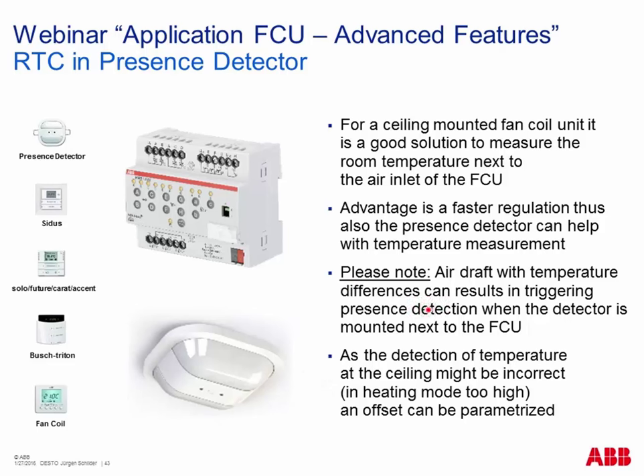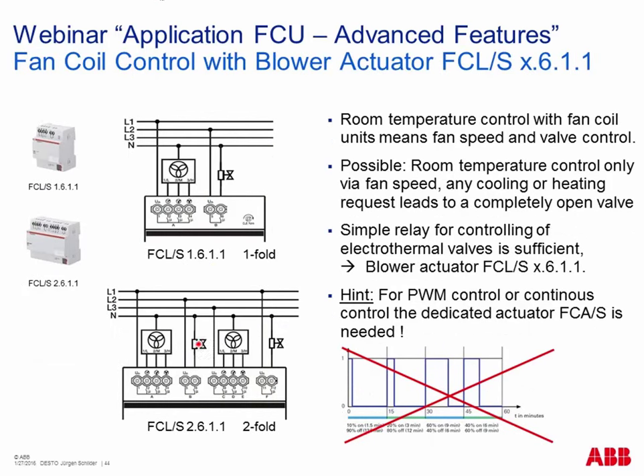For fancoil units, a good solution is to measure the room temperature directly at the air inlet of the fancoil unit — this gives a faster reaction and more precise regulation. If this component is ceiling-mounted and close to the air inlet, it could be an option. But be careful: any air draft from the fancoil unit could trigger the presence detector, which of course we don't want. If it's not too close and not triggered by air drafts, it could work. Also, if measuring at the ceiling, the temperature might read a bit high for heating — you can program an offset to correct this.